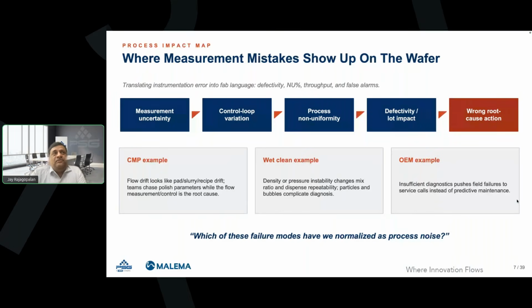Often it could be the type of selection that we make on the flow meters that leads to a defect. For example, measurement uncertainty can lead to control loop variations, which can lead to process non-uniformity and defectivity, etc. And hence a wrong diagnosis is possible. In the case of CMP, flow drift looks like a pad or a recipe drift, for example, but often the flow controller or flow meter could be the root cause. In a wet clean example, concentration or density or pressure instabilities can cause different formulations not to be maintained, and that could also create a problem. So we have to look at all these things while selecting the right product.